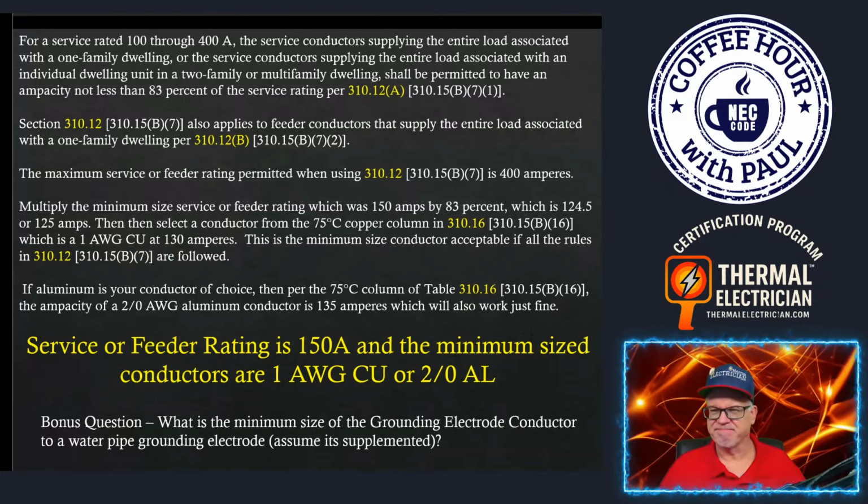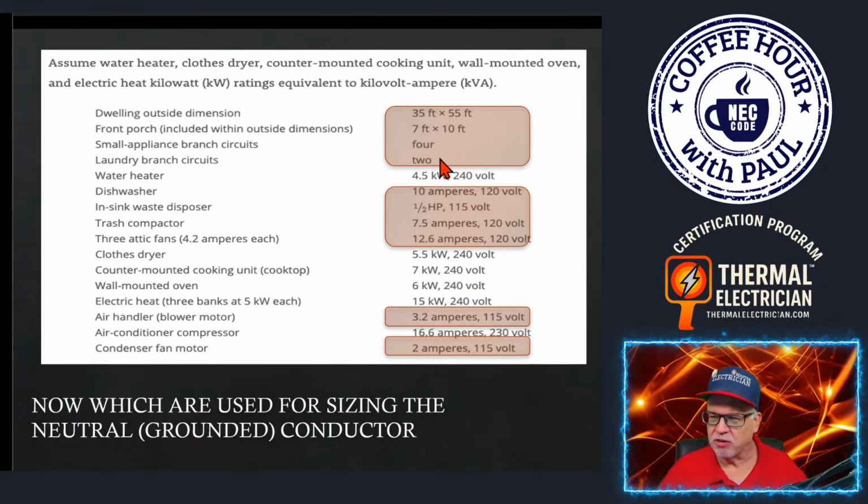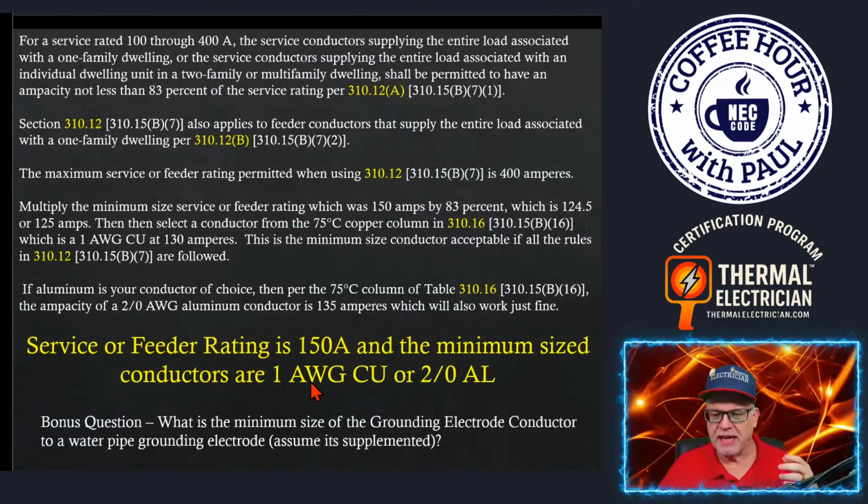Now, when it came to that neutral conductor, we won't go into this on this episode, but you remember you have to use the standard method, and I'll just show you one real quick way of doing this. Kind of move through this pretty quickly for you because I know some of you out there are going to be taking the exam. But let me explain something to you in the real world. In the real world, if I size the neutral at no more than 2 sizes smaller than my ungrounded conductor, I'm probably going to be fine. If you want to size it full size, you're probably fine.